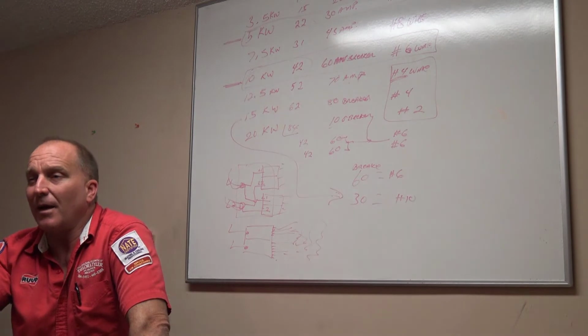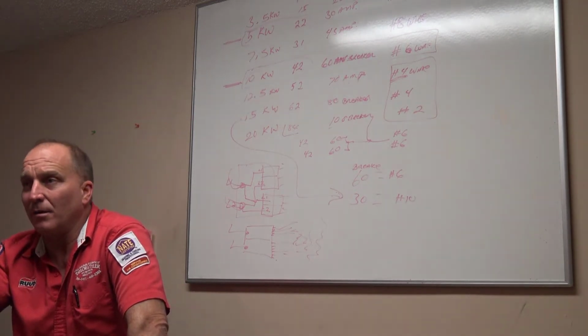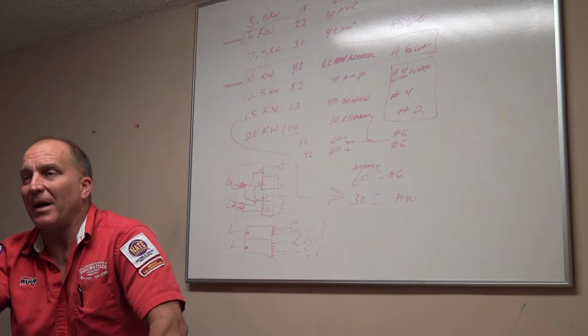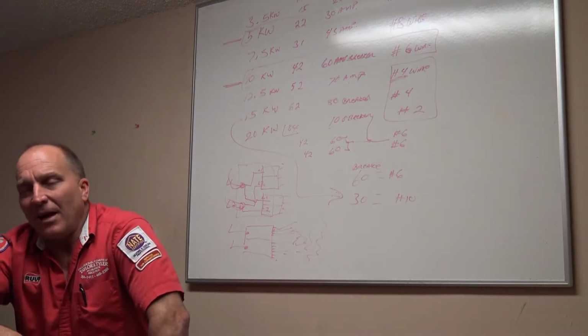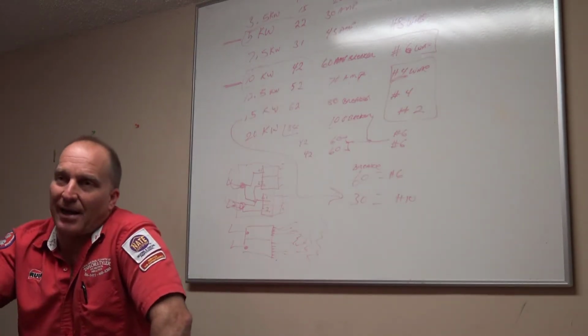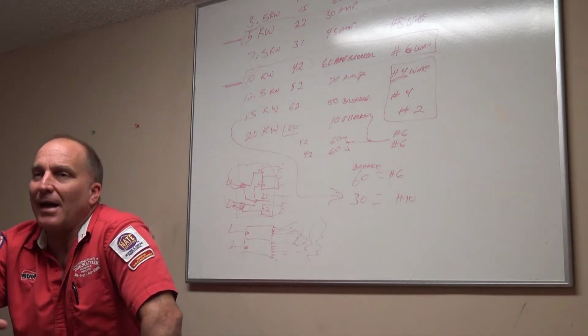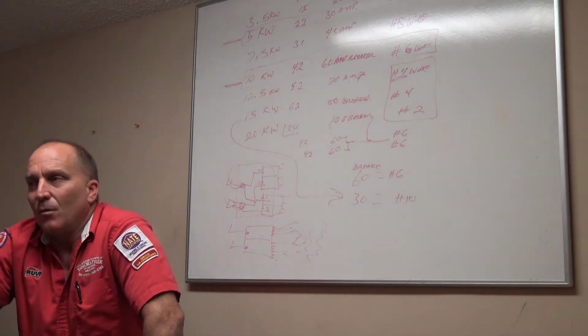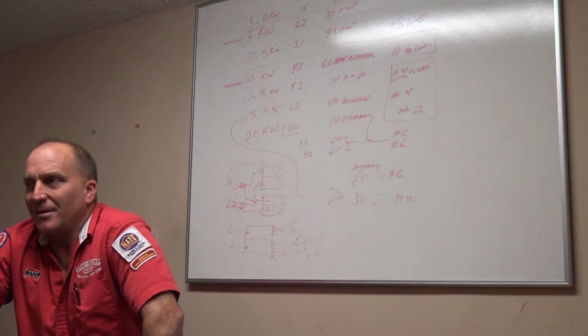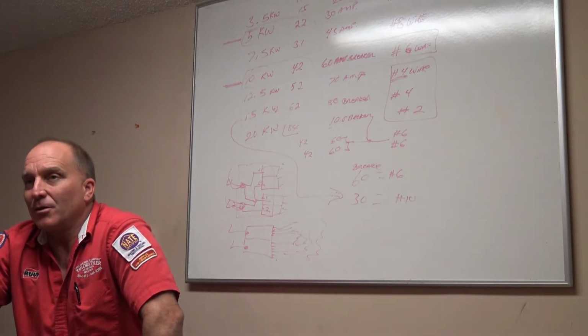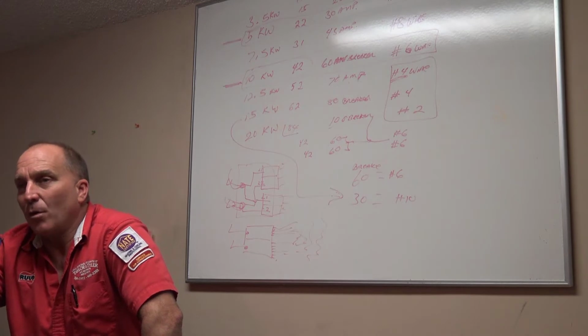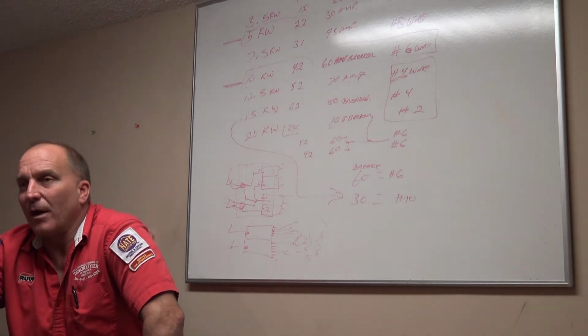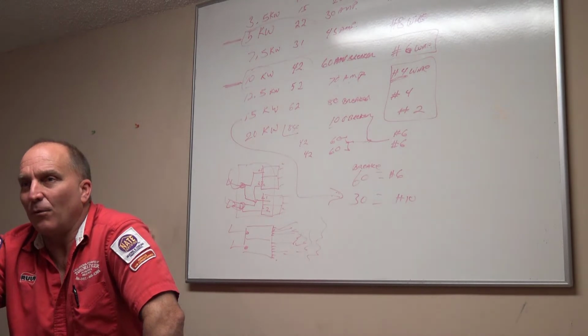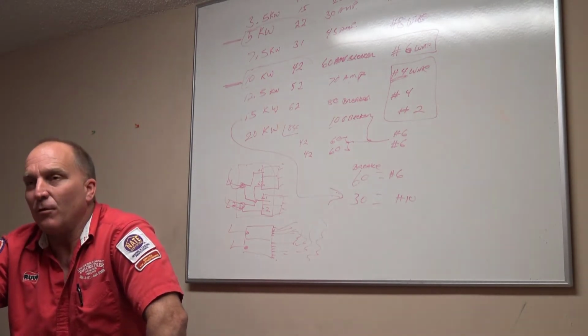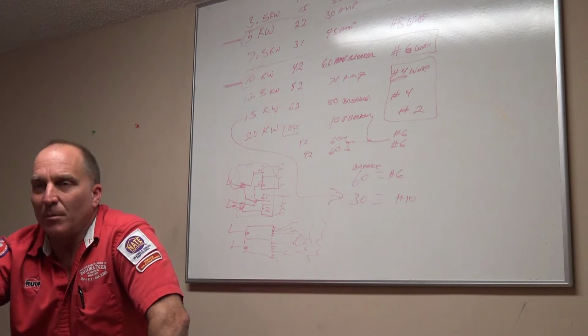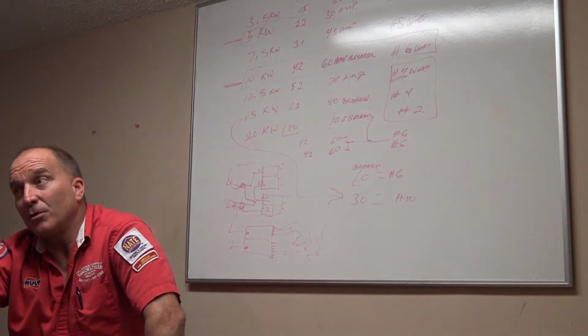Does everything ignite? Does your burner come on? Does it run? Does your blower motor come on now? And am I heating the home? If the answers to all those questions are yes, then when you leave, guess what the last thing you need to do is? Run that heating system again and test it. The last thing you do is go to your thermostat, turn it back on before you leave, and then you go, okay, heater's working again before I walk out the door. Because what if you forgot to put that red lead back on your blower motor and your blower motor doesn't come back on? It's because you forgot to put it back on.